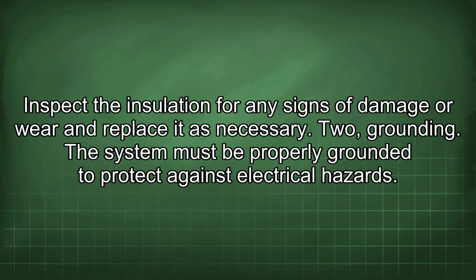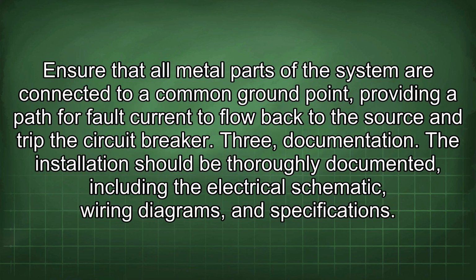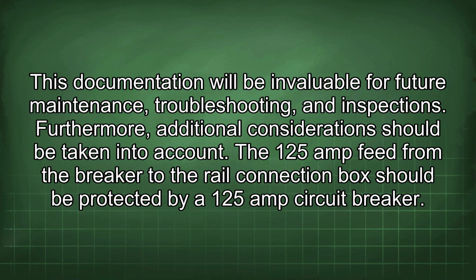2. Grounding. The system must be properly grounded to protect against electrical hazards. Ensure that all metal parts of the system are connected to a common ground point, providing a path for fault current to flow back to the source and trip the circuit breaker. 3. Documentation. The installation should be thoroughly documented, including the electrical schematic, wiring diagrams, and specifications. This documentation will be invaluable for future maintenance, troubleshooting, and inspections.